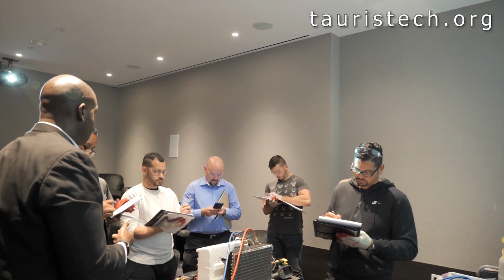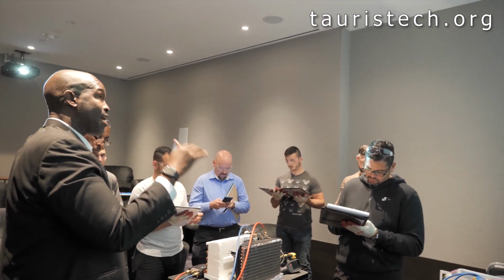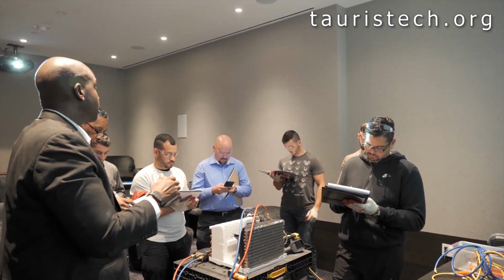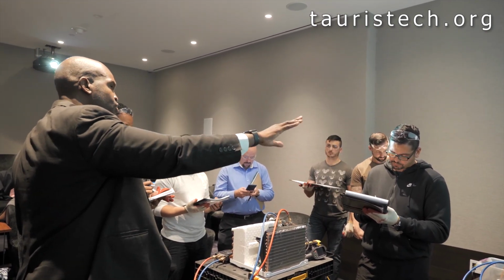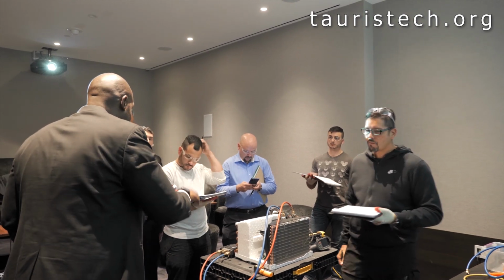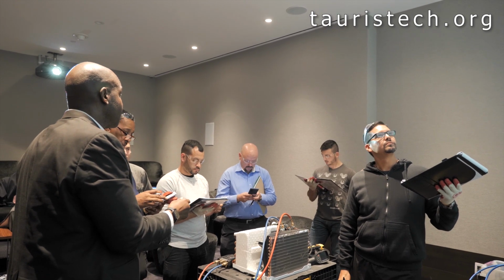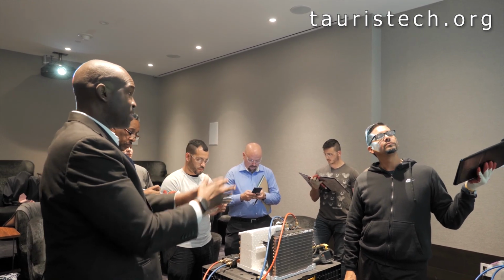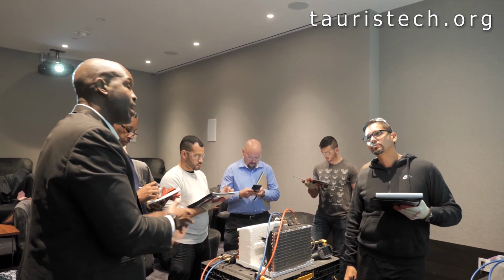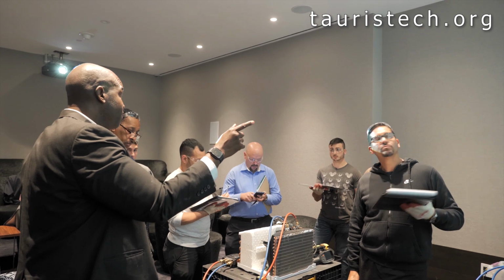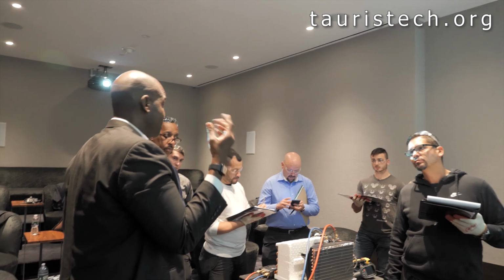The difference between our low side saturation point and our suction line temperature is our low side superheat. If I send the refrigerant at its saturation point into the compressor, what am I sending into the compressor? So let's think about the word saturation point. The saturation point is the temperature we change state at. We're sending liquid into the compressor. If I want to boil my refrigerant at 35, and it goes into the compressor at 35, there's still some what? Liquid. There's still some liquid.